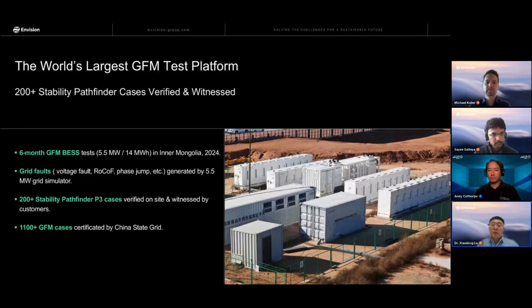The grid simulator's rated power is 5.5 megawatts as well. We used the grid simulator to simulate different grid faults like rate of change of frequency, phase jump, voltage faults and oscillation. We also used the grid simulator as the load to test our setup in islanding mode. By using this whole platform, we tested and verified our grid forming there for 6 months.